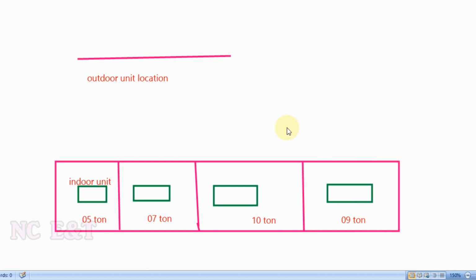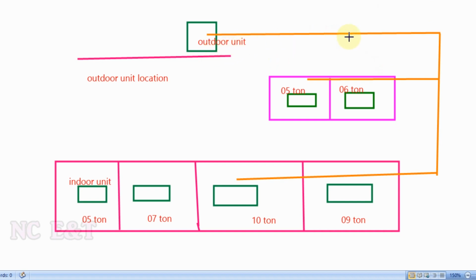Next stage, to select the location for the outdoor unit. We have selected the outdoor unit location. So now number 3 will be, let us locate the outdoor unit nearest to the indoor units, and we will measure the distance for the piping length up to the units. Now we will draw the shortest possible route for the refrigerant piping.